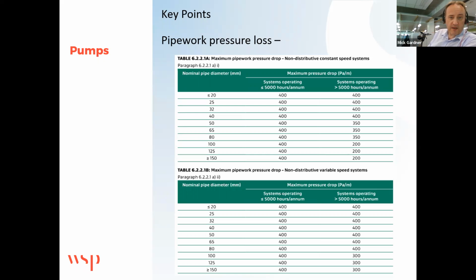So depending on the size of the pipe and also your system operating hours per annum, you'll be looking at 400 pascals per meter. As the pipe gets bigger, on greater running hours, it drops to 350 or 200. So we've got to bear this in mind when we're sizing pipework now, especially if you've got a long running system that's 24 hours. As your pipework gets bigger, you're going to get more restrictions, so this is going to increase pipe sizing.